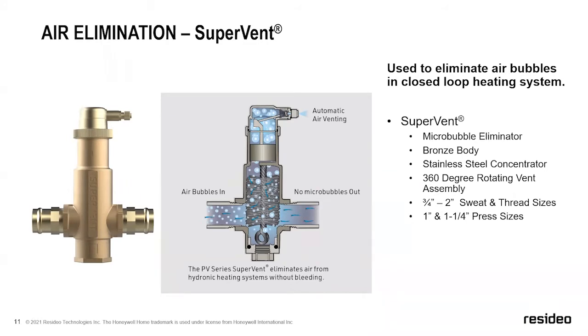So what's going to happen is that air vent's going to have the float push down. It's going to open the vent on the top, which is going to allow that air to automatically purge and come back through. So the reason we're seeing a very large, and this has been taking place over the last 10 years, we've seen a very heavy migration from air purgers or air scoops into this type of an air elimination device, is because it's much more effective at collecting the micro bubbles. So when you pass through this, if you're entering at 4 feet per second velocity, you're going through it at 4 feet per second and coming out, you need something that's going to catch those little micro bubbles. This does a very effective job.